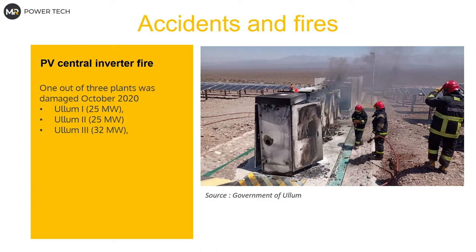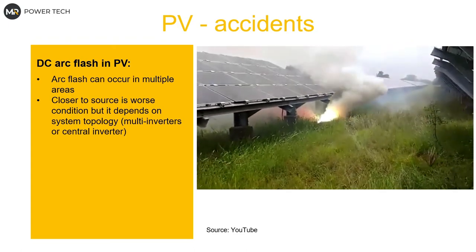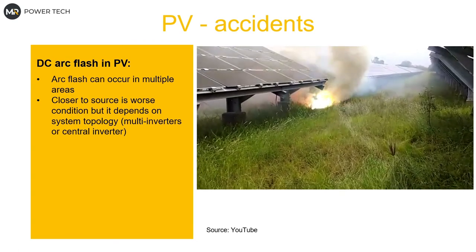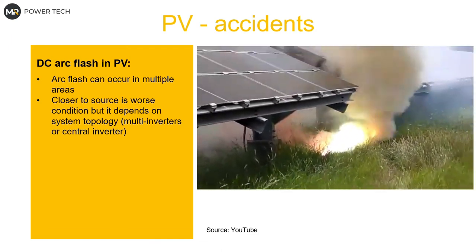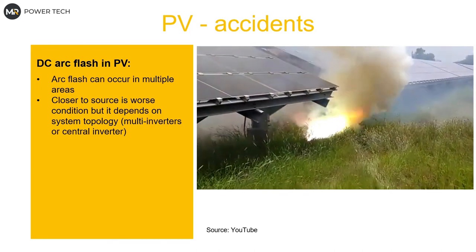There have been fires from this. There was a fire in Argentina at one of the central inverter plants — the inverter burned and there was little the firefighters could do. If you look at YouTube recordings of PV string cable or combiner box fires, the only thing you can do is cut the cable, which is not a very safe action unless you know exactly what you are doing.